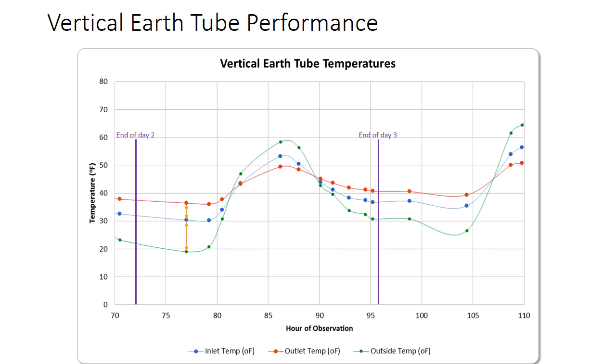I picked about a day and a half to highlight. Here at hour 77, notice how the air temperature outside is about 19 degrees Fahrenheit. The temperature inside the greenhouse is about 31 degrees Fahrenheit, so we're comfortably 11 degrees above. The system is doing the job of keeping the greenhouse partially warm, even though it's a small system.